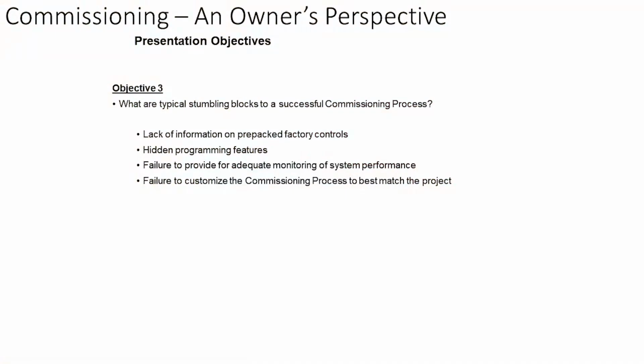More stumbling blocks: a lack of information on prepackaged factory controls. Like I said, that's why we've gone away from prepackaged factory controls. Hidden programming issues — unless you do the full-out testing and test every response of the software programming, you're not going to hit those programming issues.